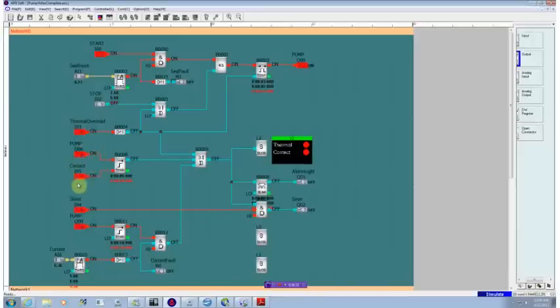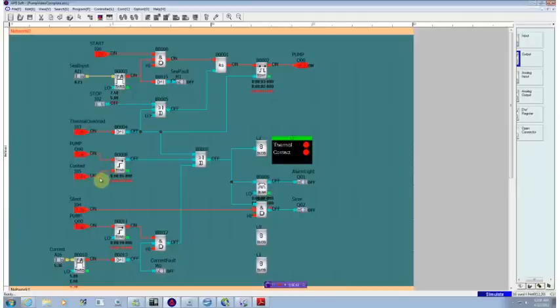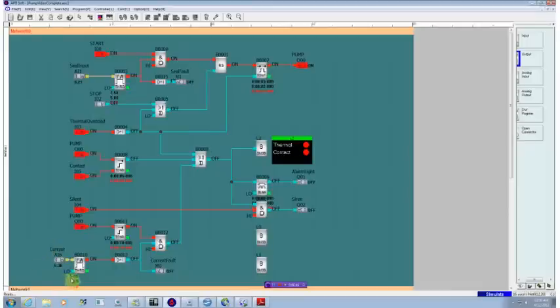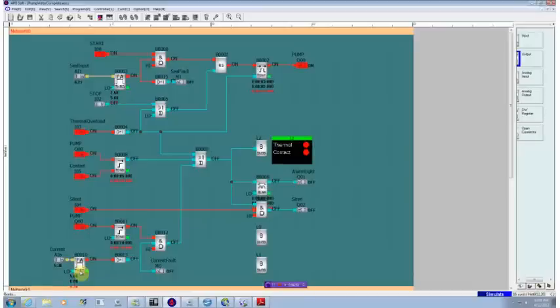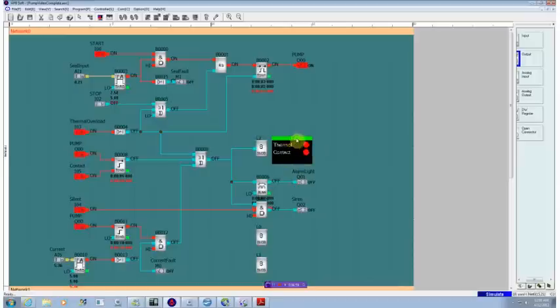We've put in feedback from the contactor so that we know that when the pump output actually goes on, it turns on the contactor. And then we've added in current monitoring capability to know that the motor is running within a specified load and there's nothing jamming or impeding the flow of the liquid.